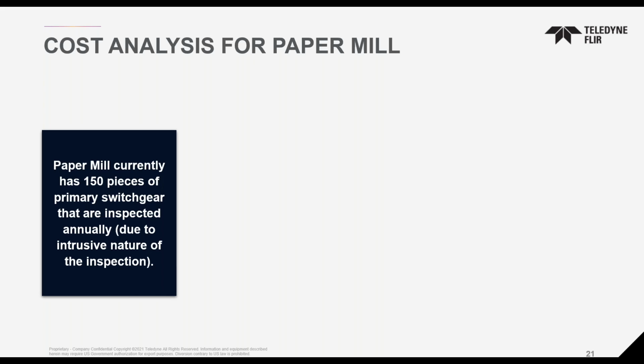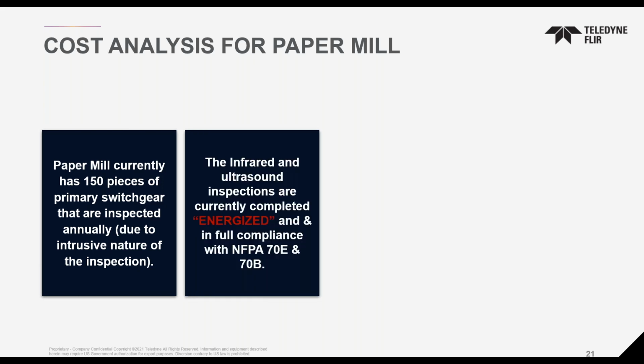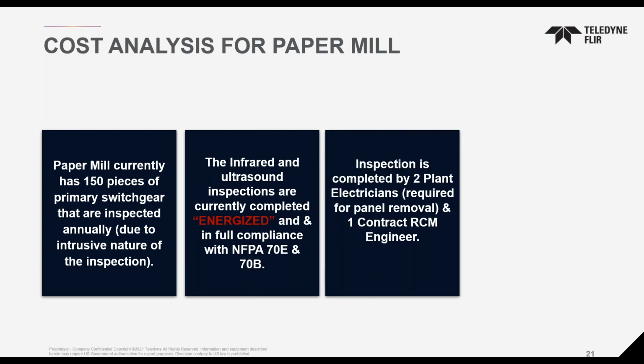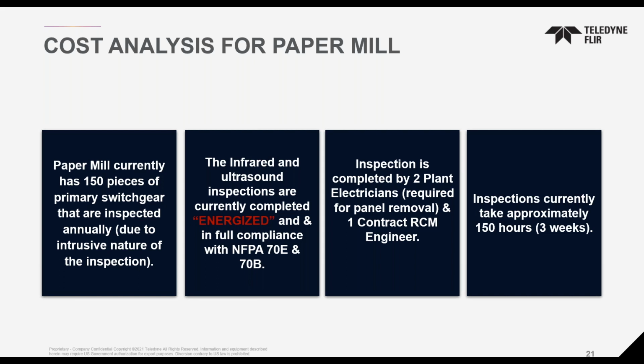Working with a paper mill, they're performing inspections of about 150 pieces of primary switchgear annually. It's a pretty intrusive inspection, using a combination of infrared and ultrasound, done in a completely energized environment, needing to be in compliance with NFPA 70E and 70B. It's done by two plant electricians, one required for removing the panel, plus a contract reliability-centered maintenance engineer actually performing the inspections. It takes about 150 hours to perform - this was the baseline for their current work practices.